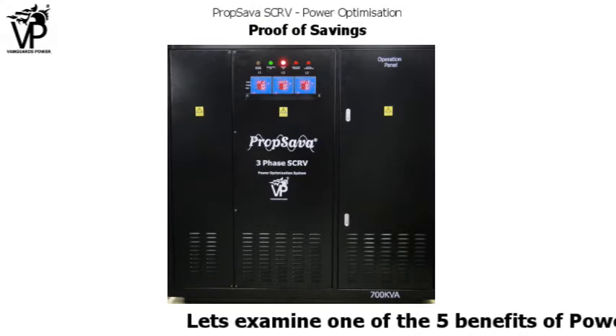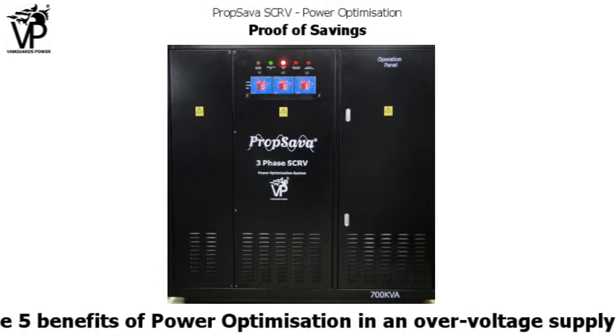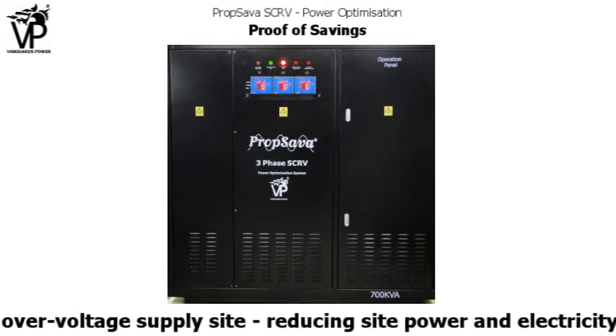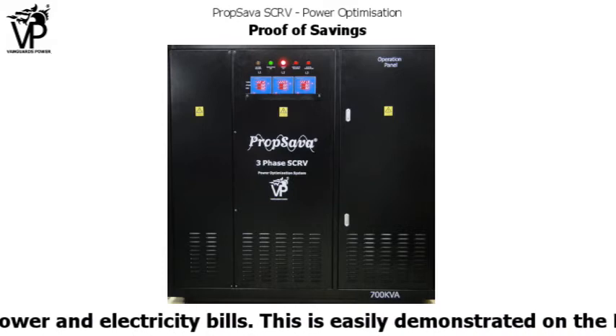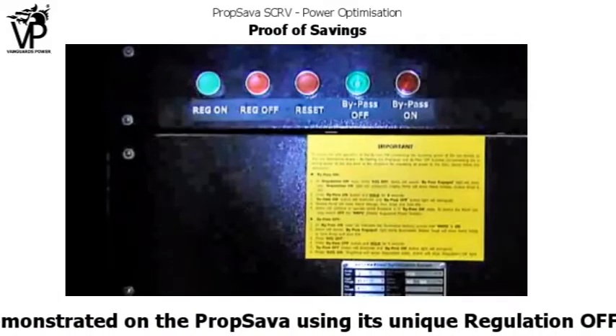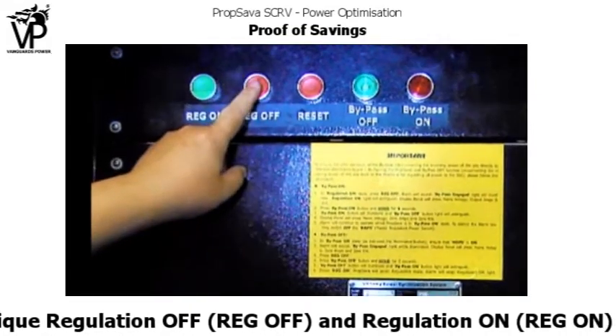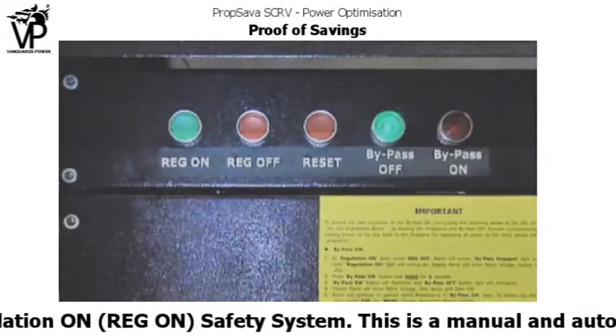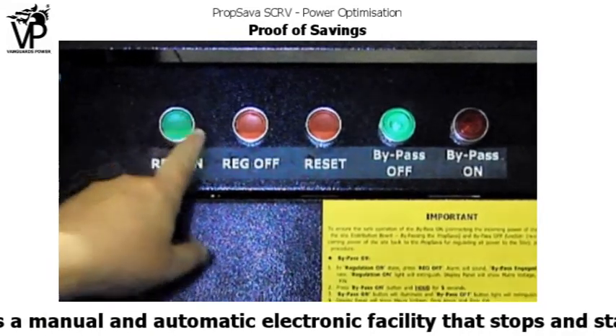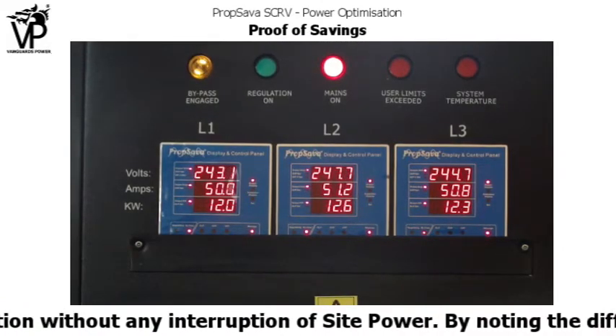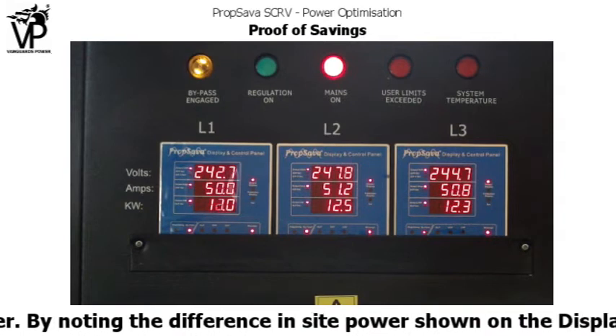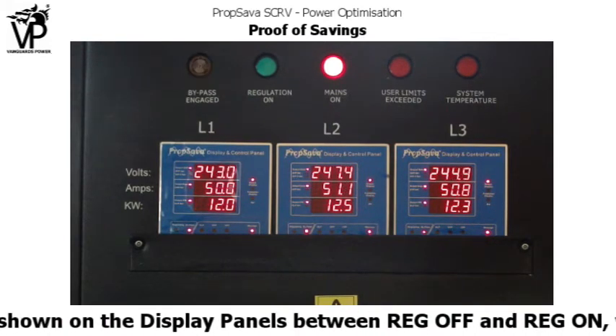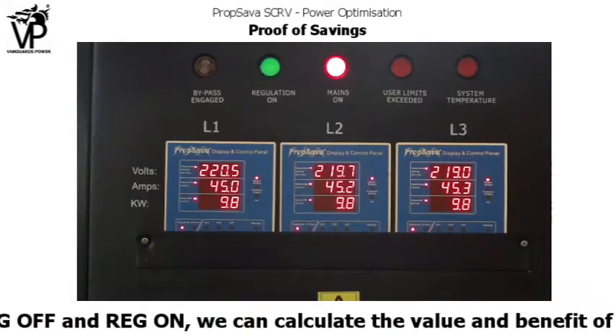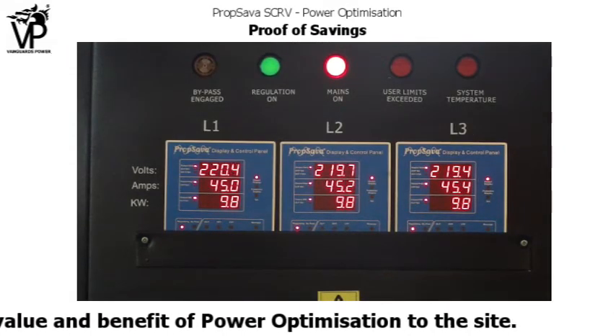Let's examine one of the 5 benefits of power optimization in an overvoltage supply site: reducing site power and electricity bills. This is easily demonstrated on the PropSava using its unique regulation off (reg off) and regulation on (reg on) safety system. This is a manual and automatic electronic facility that stops and starts PropSava regulation without any interruption of site power. By noting the difference in site power shown on the display panels between reg off and reg on, we can calculate the value and benefit of power optimization to any site.